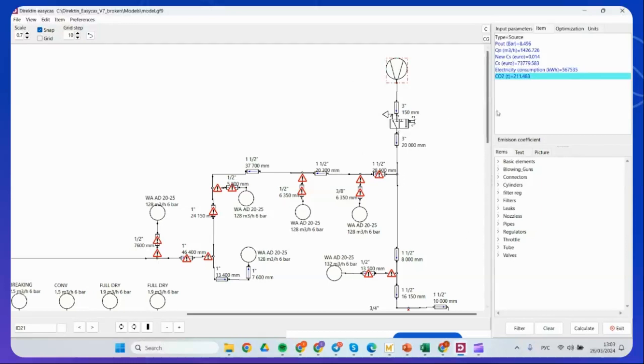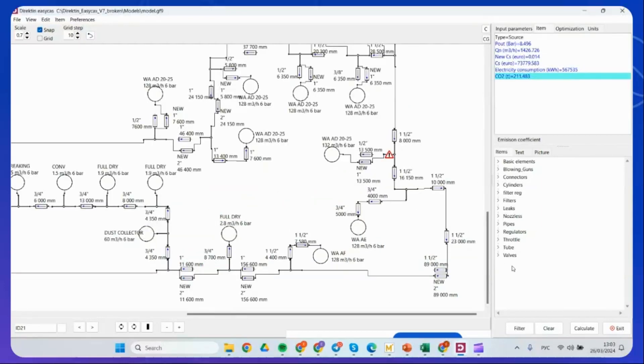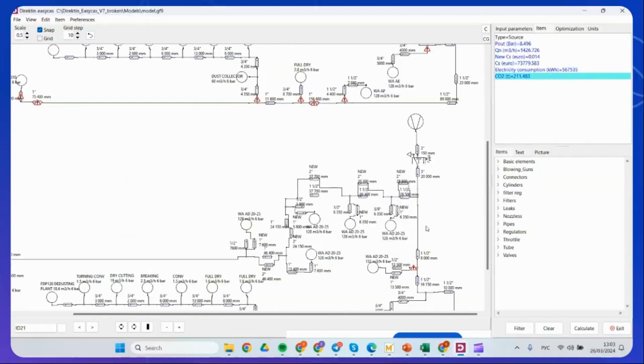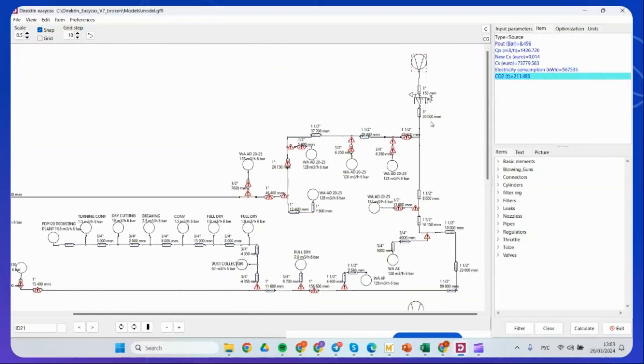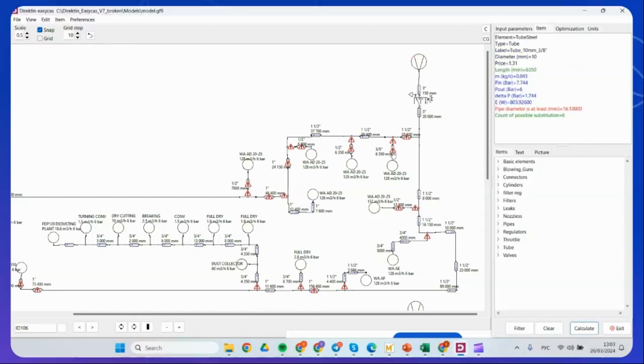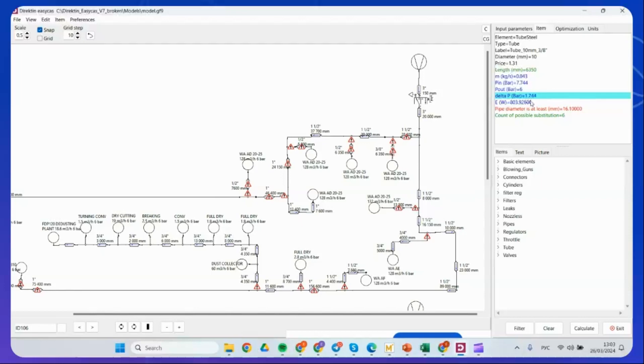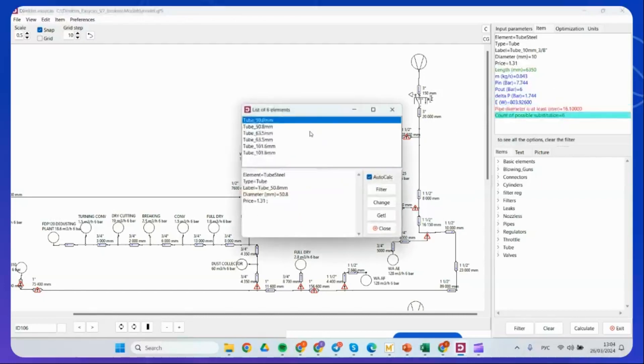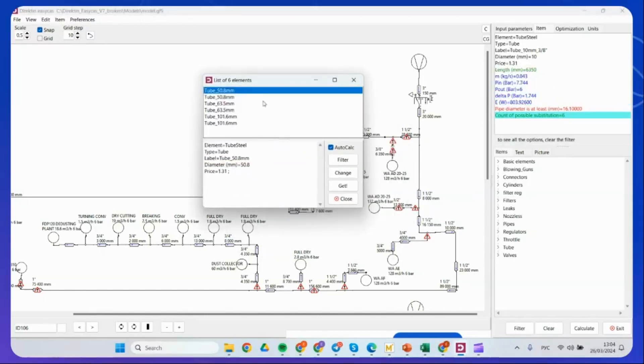After this, you can actually copy this system and start optimizing it. Here I have two systems copied. I'm optimizing it. And here now, because I don't want to work on the demand side, I just want to check the design. I need to go and check the pressure drops. And the system tells me, listen, here delta P is very high. 1.7 bar, it's a lot. To avoid this pressure drop, you need to choose the pipe diameter at least with this diameter. And then I go into the database and change it.